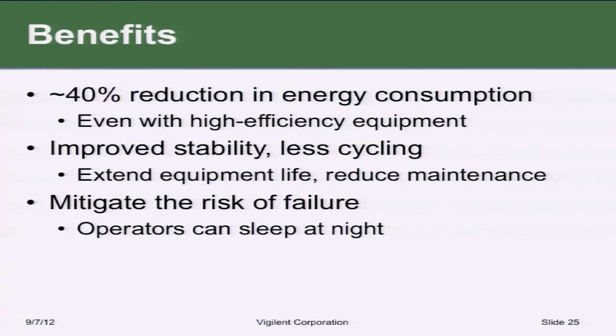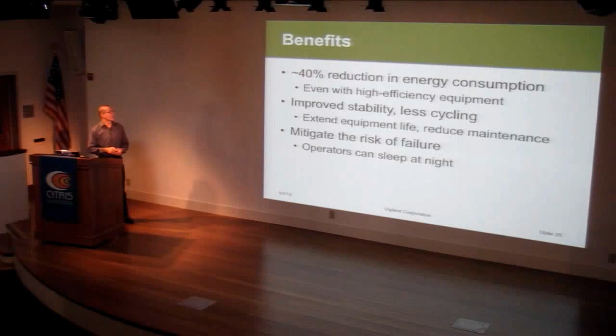And so if you had 200,000 cycles on your compressor, if you cycle them very fast, you don't get 200,000. You get 100,000 or 50,000. And you're doing it faster, so it ends up failing. Instead of, say, 15 years, you end up failing in a year. So, the benefits of being able to solve these stability problems: a big reduction in energy consumption. We typically see that if you have one of these data centers that's over capacity, really thrashing around a lot, we can get about a 40% reduction, even in these ones where they have hyper-efficient air conditioning. And that's because of the system effect.